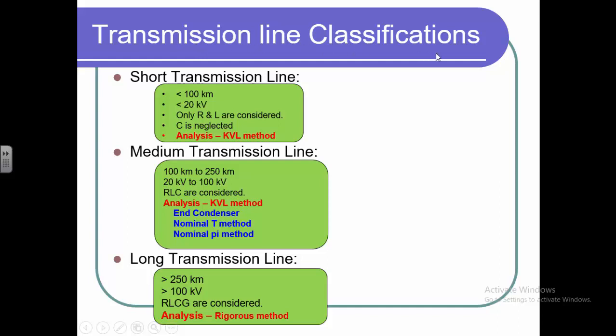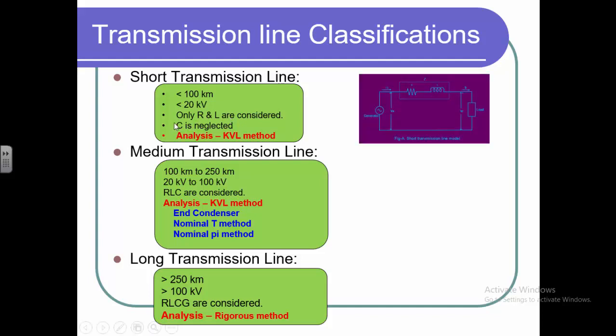We can classify the transmission line into three categories depending upon the distance and the voltage level. The first one is a short transmission line, the second is medium transmission line, and the third is long transmission line. For short transmission lines, the span is less than 100 kilometers and the voltage is less than 20 kV. In this short transmission line we are only considering resistance and inductance. Capacitance is neglected because the capacitive reactance is so small compared to the inductive reactance.